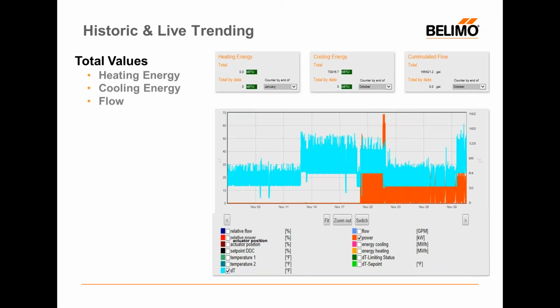We have a couple pages for trending. We have a data log chart and a historic trending chart. And here you can take a look at either what has been going on in the valve historically, so you can actually reference the existing data that's stored in the valve, which is stored for either up to 31 days in short term or 13 months in long term, or you can do a live trend, so you can actually select some points you'd like to look at, say the DDC input from the controller, maybe the flow and the associated delta T, and watch them run live for an hour period of time.